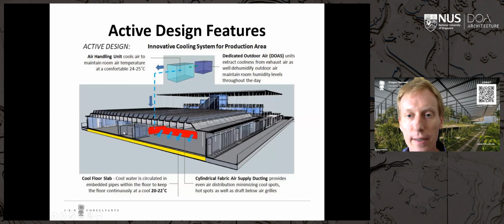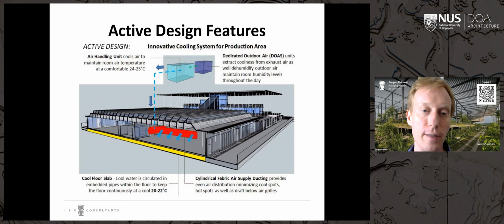For cooling, we put slab cooling into the concrete slab for the entire factory hall as well as the office spaces, so about a third of the cooling was done this way. This factory had various ovens creating a substantial amount of heat, and since that's basically sensible heat, it can be cooled quite effectively with sensible cooling from a floor slab cooling system.